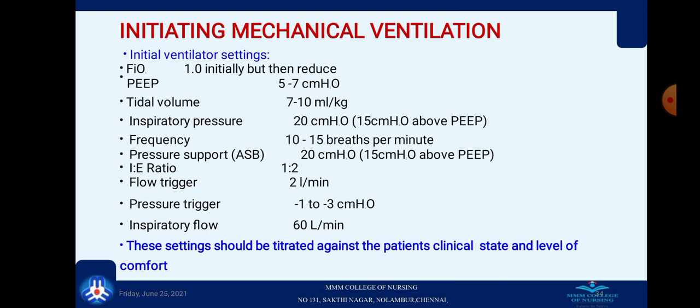inspiratory expiratory ratio 1:2, and flow trigger 2 liters per minute, and pressure trigger -1 to -3 cm H2O, and inspiratory flow rate 60 liters per minute. These settings should be titrated against the patient's clinical state and level of comfort.